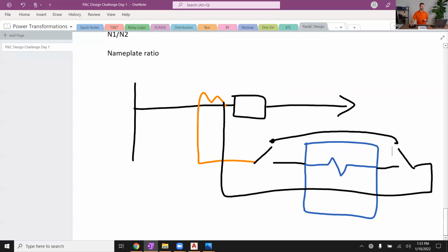But on the CT secondary, still connected to the possibly still energized primary, you can have current flowing around this relay terminal and back to the neutral just fine, even though the relay is showing no current at that point. So hopefully that gives you a good feel for the general premise. You're going to look at that again on a real life, actual, a little prettier CAD drawing, 1-line, 3-line rendition tomorrow, and you get to see that again. But this is the essence of what we're after.